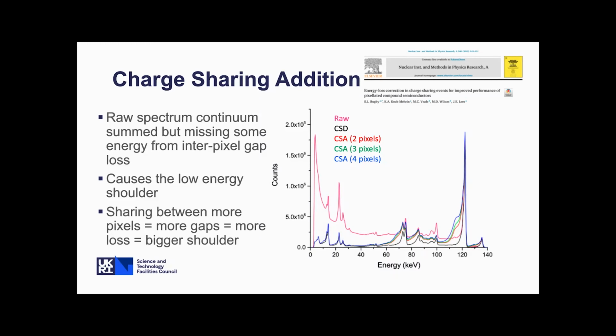So what's happening here, we've got the pink spectrum, which is the raw data with the charge sharing continuum again. In black, with the low baseline, that's the charge sharing discrimination. And then when we add in the charge sharing addition, you can see with the red, green, and blue, as we add in more pixels, we're getting a higher fraction of this low energy shoulder. And that's because we're missing some of the charge, because it's going in that interpixel region.